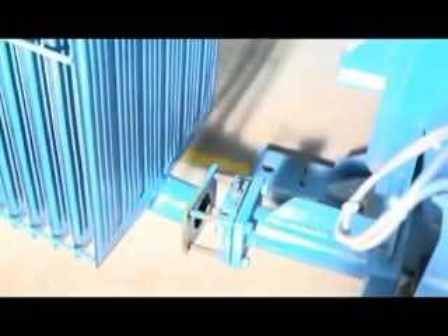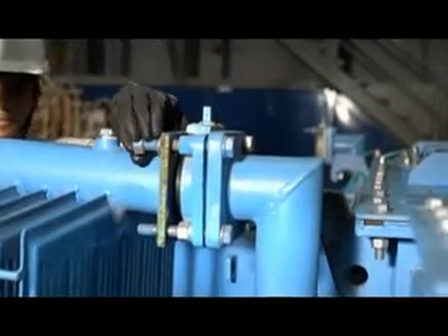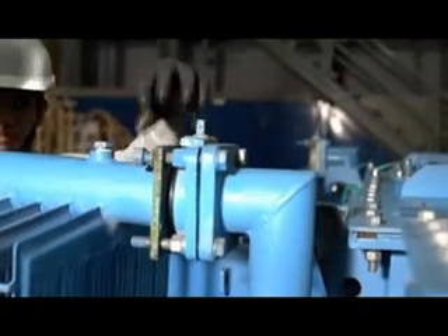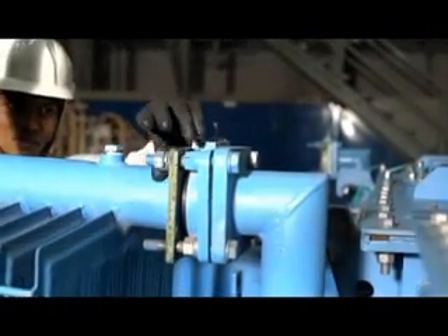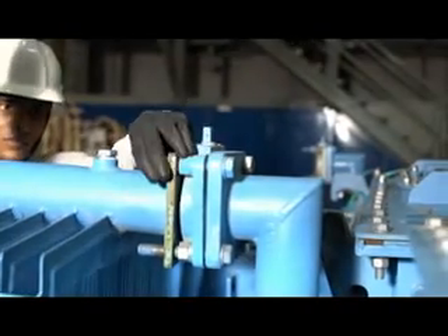Now remove the blanketing plates of the main tank valves. Fit the radiator flange on the respective valve of the main tank with nuts, bolts, plain and spring washers. Assemble all the other radiator units in the same manner.